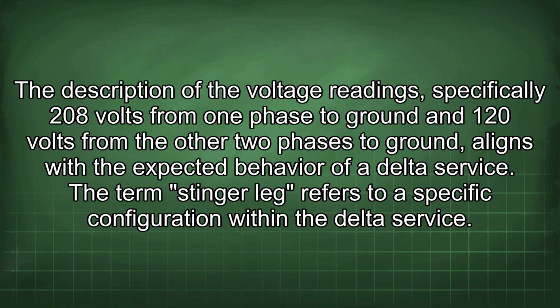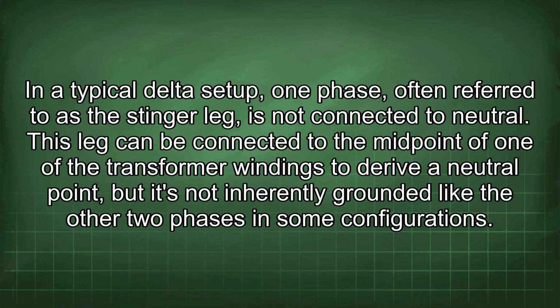The description of the voltage readings, specifically 208 volts from one phase to ground and 120 volts from the other two phases to ground, aligns with the expected behavior of a delta service. The term stinger leg refers to a specific configuration within the delta service. In a typical delta setup, one phase, often referred to as the stinger leg, is not connected to neutral. This leg can be connected to the midpoint of one of the transformer windings to derive a neutral point, but it's not inherently grounded like the other two phases in some configurations.